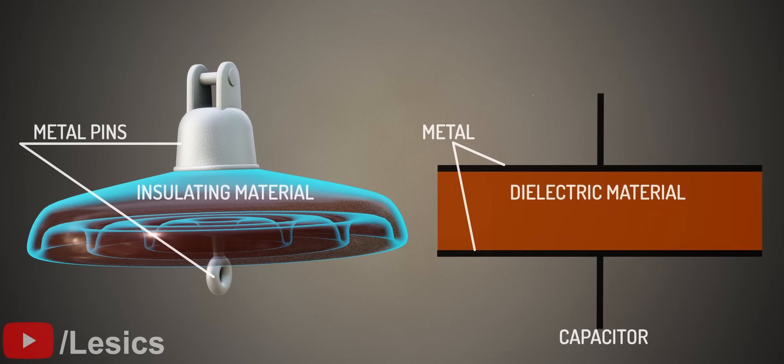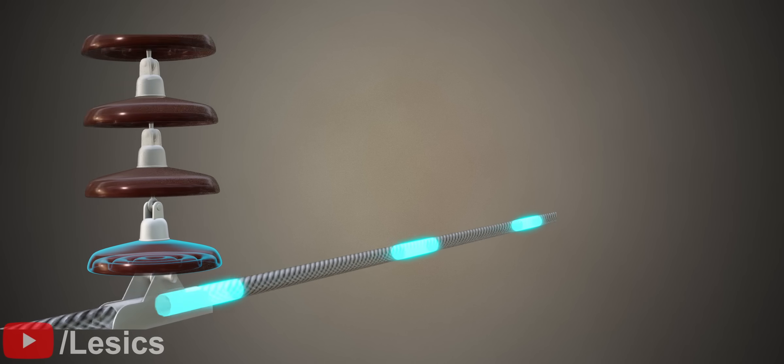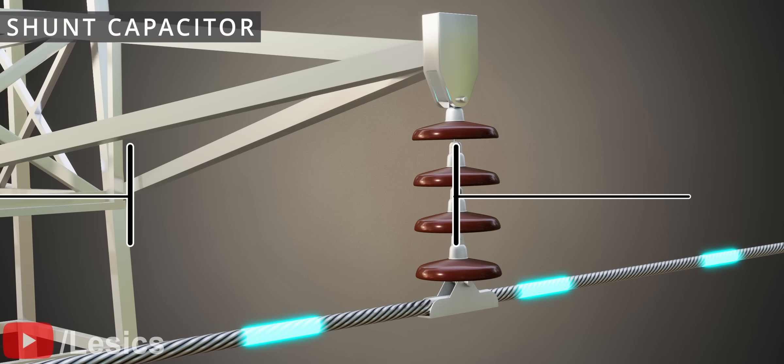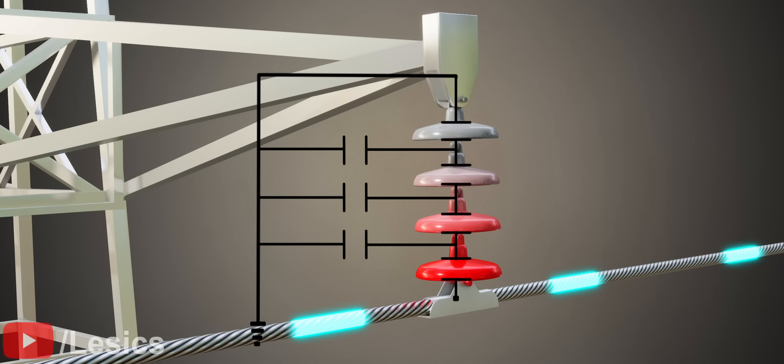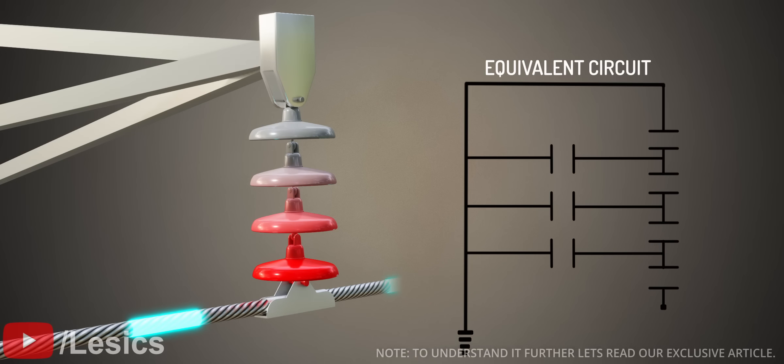Let's see how this unequal voltage occurs and how we can avoid this. Here, you can observe two metallic pins of the insulator acting as capacitor plates with a dielectric between them. Similarly, there is one more type of capacitor that forms between the tower and metallic pins, in which air acts as a dielectric. The unequal voltage distribution is caused by this capacitance effect.